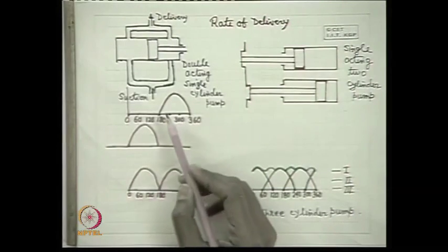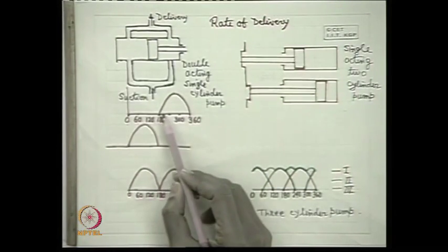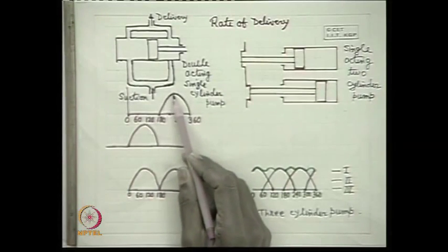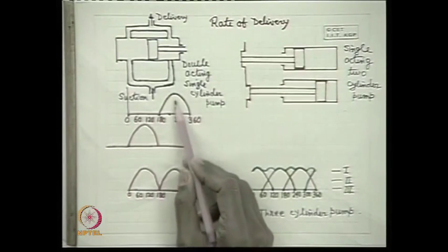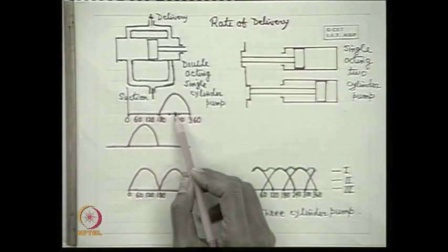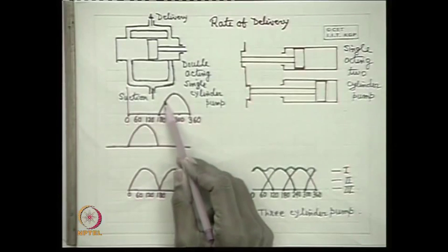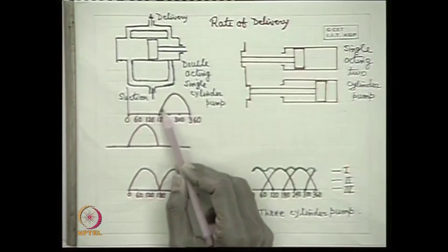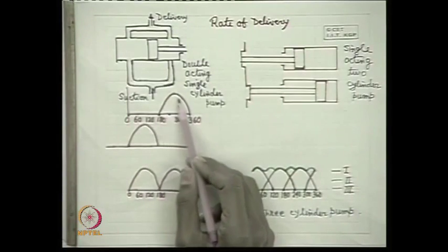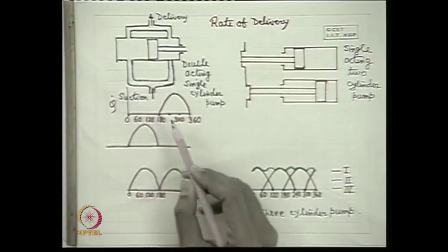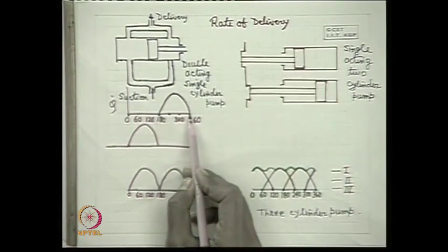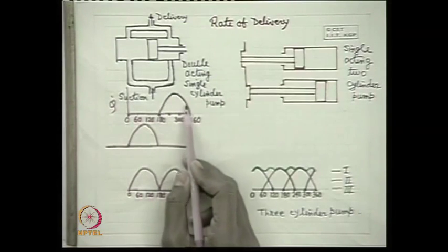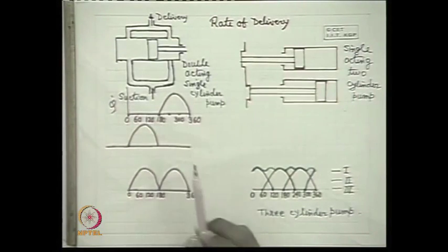And as you have noticed, the velocity in the delivery pipe varies periodically because of the acceleration and deceleration head. It is zero and then goes on increasing, attaining the maximum at the mid of the stroke, considering a simple harmonic motion of the piston and simultaneously of the liquid column in the delivery pipe. So the velocity follows this sinusoidal distribution, and similarly the delivery, that is the flow rate Q dot. Therefore, we see the delivery occurs only from 180 degrees to 360 degrees of rotation of the crank, and that is also a non-uniform delivery.